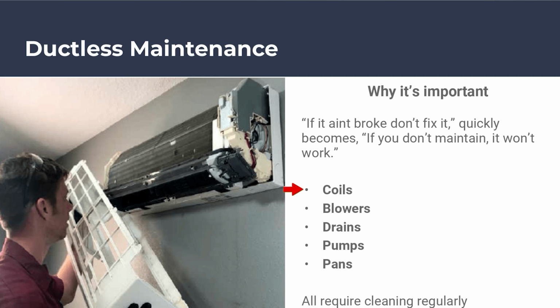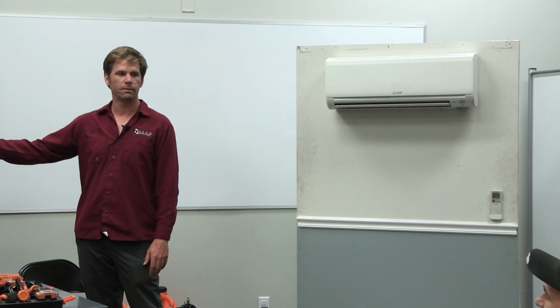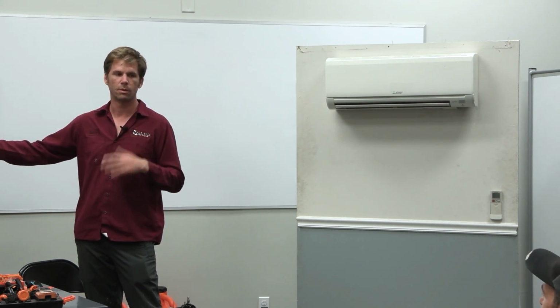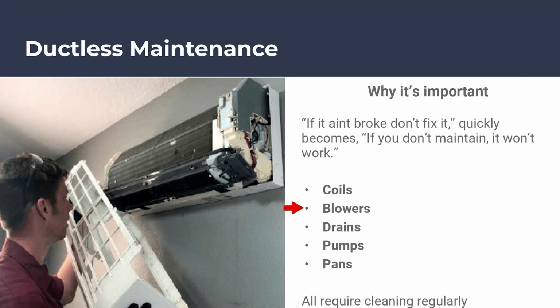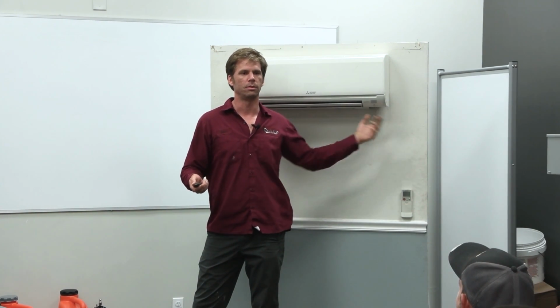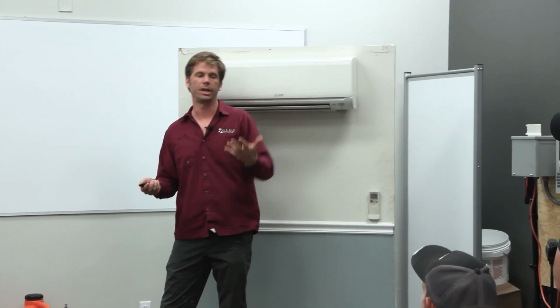That's where you get complaints about smell, the customer smells something when the unit comes on, typically algae growth inside the coils. The bib kit is perfect for that, you can use a pressure cleaner to wash it out. Blowers also gunk up and get pretty nasty, and drains and pumps are a huge issue too. We'll go over each of these individually. Pans can gunk up and clog at the exit port where they connect to the drain, with buildup that breaks loose over time and clogs right there. I've seen that several times, so cleaning out your pans is important. Let's jump into all of these things.